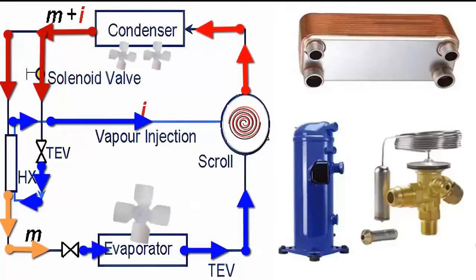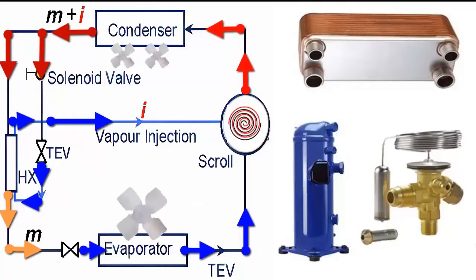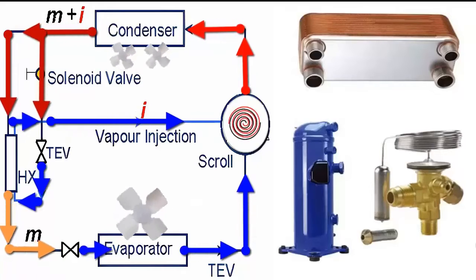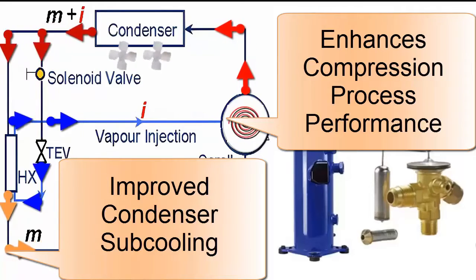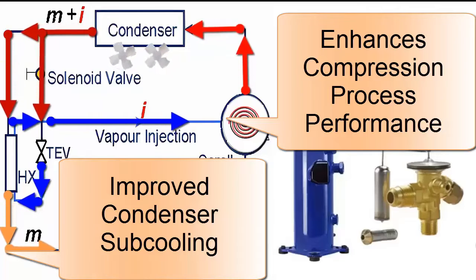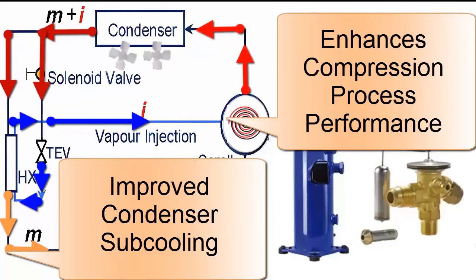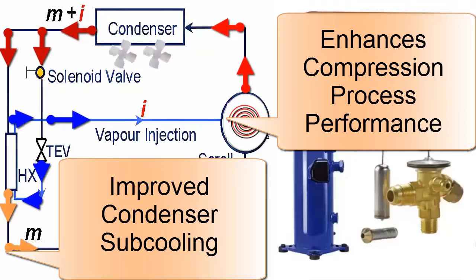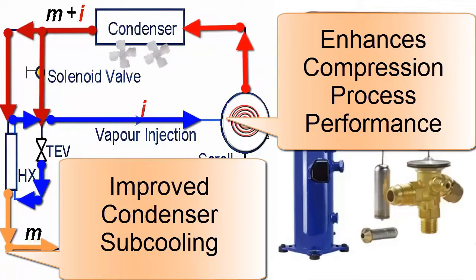The efficiency of this cycle is superior to that of conventional single-stage scroll compressors. Improving refrigerant sub-cooling at the condenser outlet increases cooling capacity, and cooling during compression within the scroll compressor improves overall refrigerant gas compression efficiency by resembling a two-stage compression.